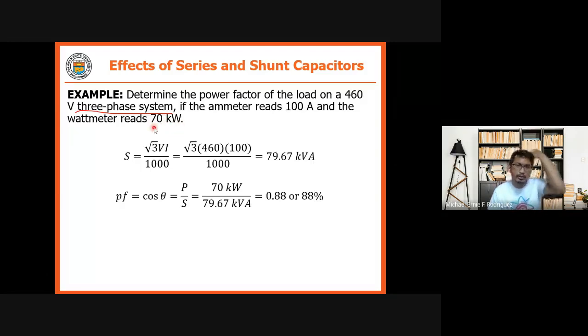Since the kilowatt value is given, that is P. And we're given V and I, so we can get the power factor. The formula for power factor is cosine theta, which is also P over S. We have P given, and we need S, which is the square root of 3 times V times I, divided by 1000 so the answer comes out in kVA—square root of 3 because it's a three-phase system.